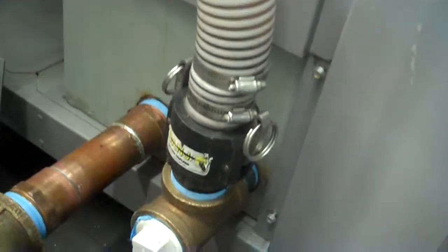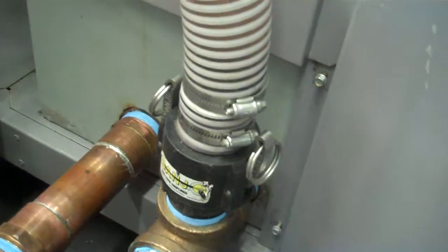It has dual process pumps in a configuration to act as backup. This here is the enclosure where the process pumps terminate down below here. Within this enclosure is actually a Y strainer, which we have actually taken out and cleaned already. Also within the process piping of this chiller, it already has a built-in flow switch, so all that's taken care of. Also part of the hydronic package is there's an expansion tank in here if you are using a pressurized fluid loop. The process piping is actually 2-inch. On the left there is your from process, and on the right is out to process.